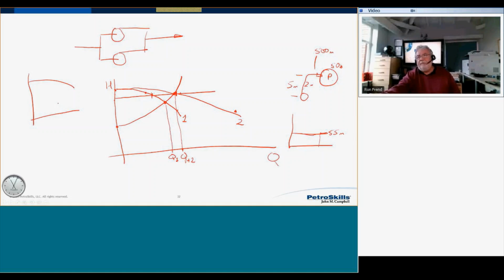I got involved with a system in North Africa on a long pipeline, and they already had some big pumps in. They wanted to put some bigger pumps in. So if this was the curve of the really big pump, that was the new one, and this was the curve of the pump that was already in existence, when they ran the two of them together, the little pump didn't add anything until you got down to about here. And on the system curve, your new pump took all of the flow and it was deadheading the old pumps. And the old pumps were just tripping out in high vibration.